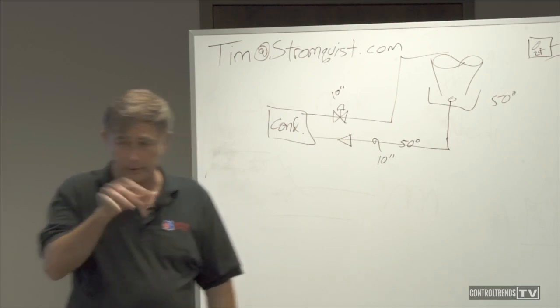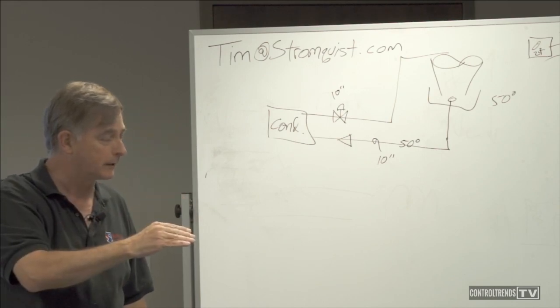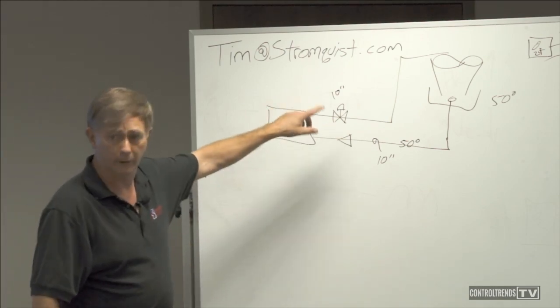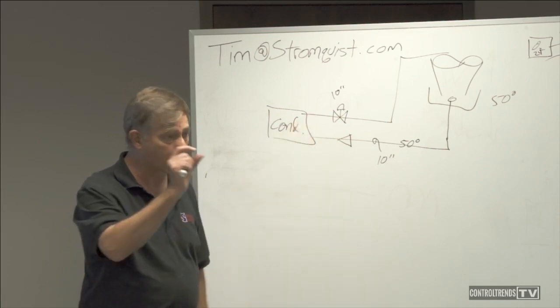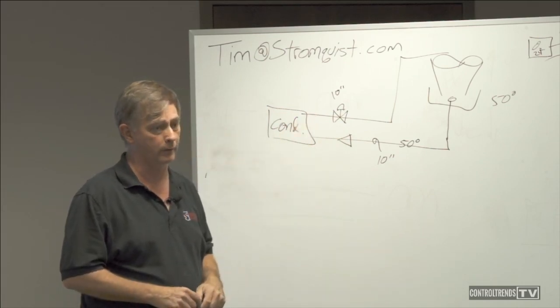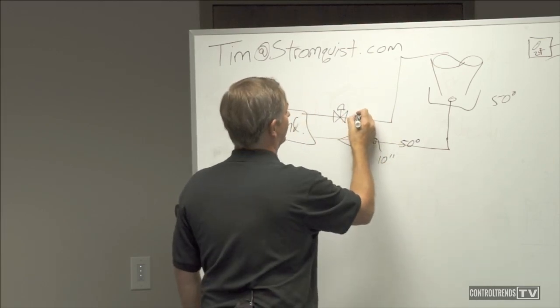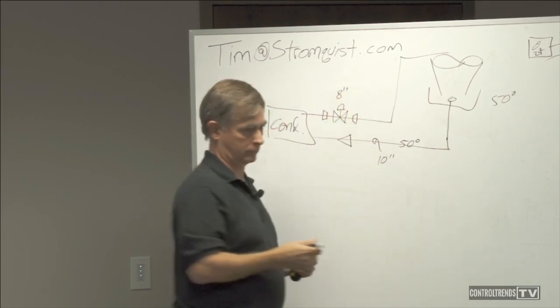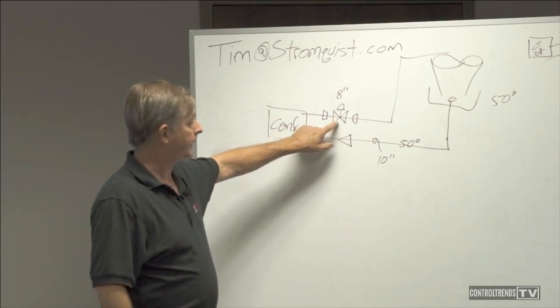It's going to be 10-inch, right? Probably. It shouldn't be. That's a mistake. But often, if it's being installed and the pipe fitter sees the drawings, he's piping up 10-inch pipe. Here, in the plans, it calls for this valve. But if it doesn't say what size valve, they're just going to go with 10-inch because it's a whole lot easier. Now, you take a 10-inch butterfly valve and you crack it open just a little bit. You send it a couple volts or 3 volts, and it cracks open. Guess what? 50-degree water. You've already got too much water. Because a 10-inch valve, you crack that thing open a little bit, you've got massive amounts of water.